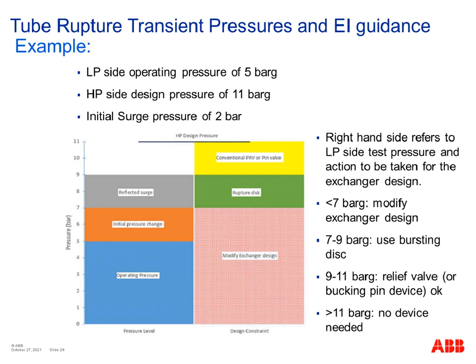So just to go into that a bit more in terms of an example, hopefully to demonstrate this a bit more clearly. Imagine that you've got a heat exchanger where the LP side operating pressure is 5 bar gauge and the HP side design pressure is 11 bar gauge. The initial surge pressure on tube failure is 2 bar. So looking at the left-hand side of the columns there on the schematic, on the graph, the blue is the operating pressure of the LP side, so you've got 5 bar there. Where the first surge comes through, you've got the initial pressure change, which is another 2 bar, taking you up to 7 bar gauge overall.